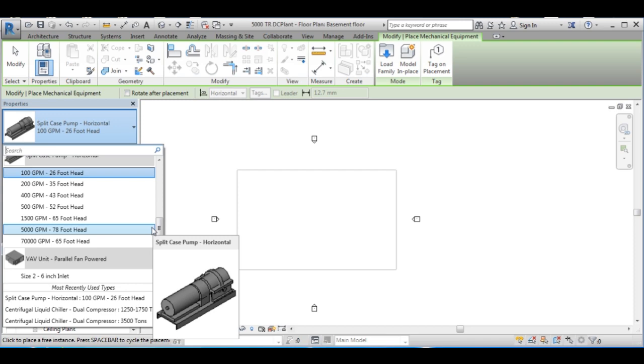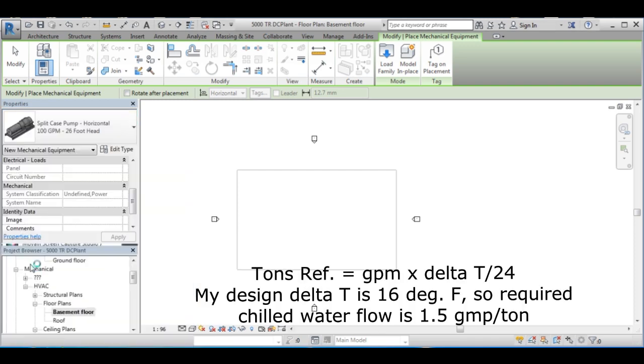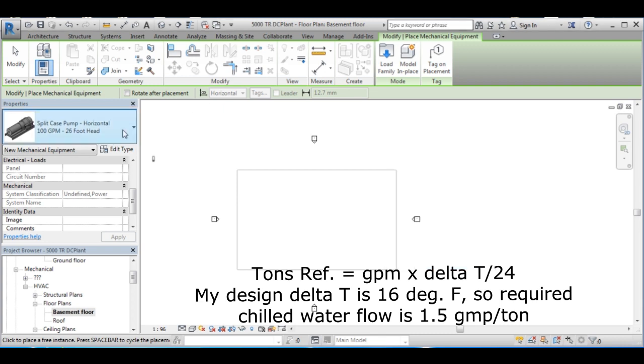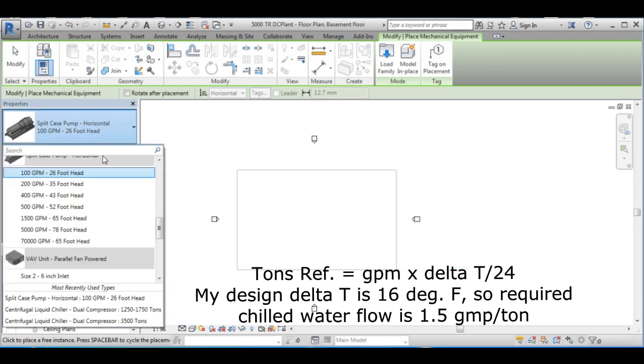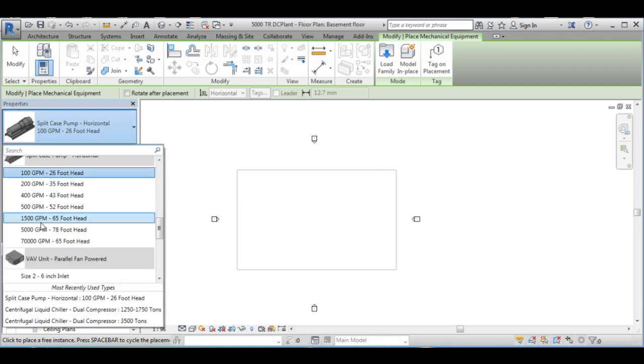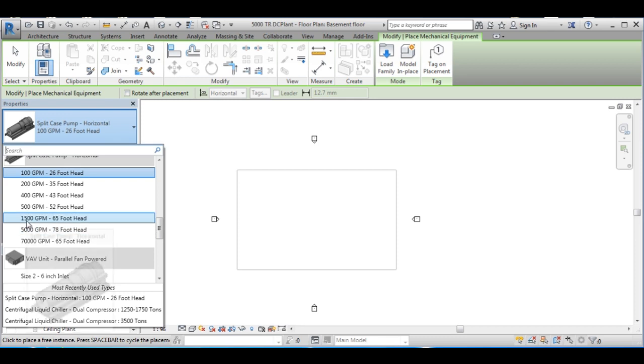Now we have to do the selection of this pump. The required flow from the primary pumps is 1.5 times the chiller's tonnage capacity. Now as I know the flow, I am going to choose a pump that has the nearest flow rating and adjust its parameters.